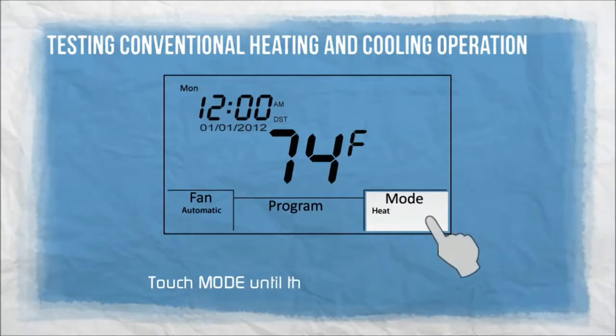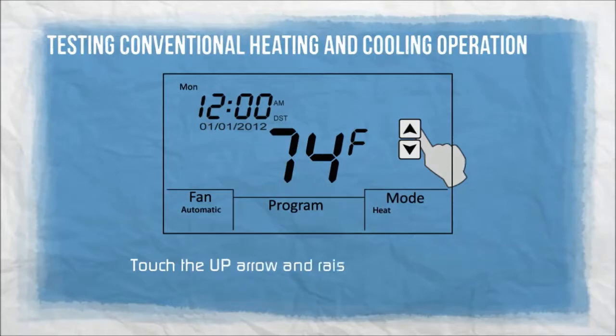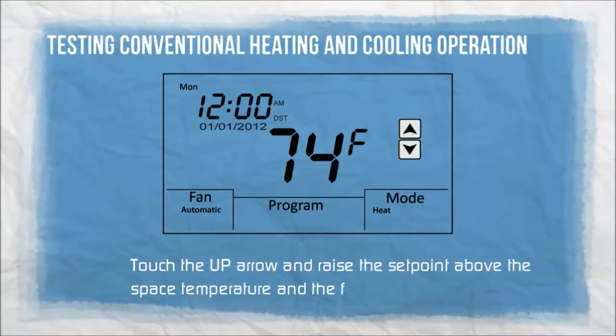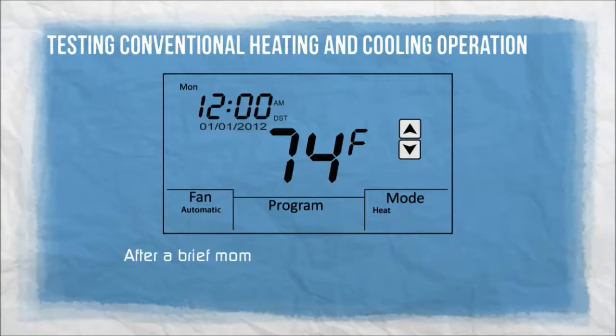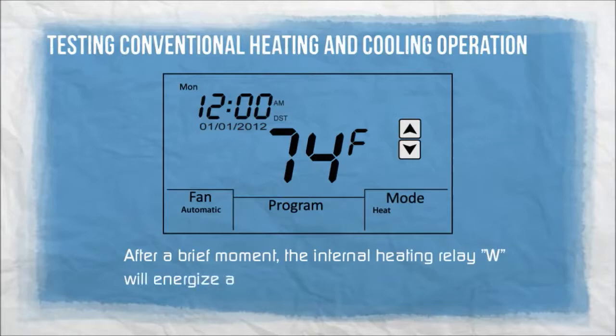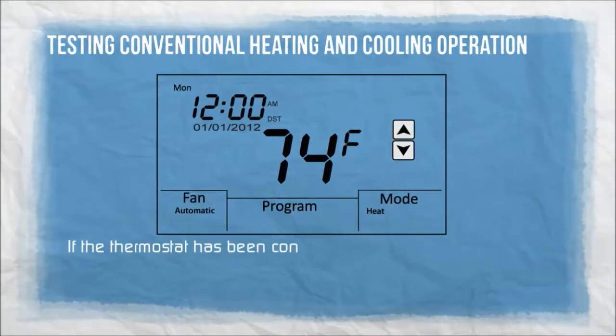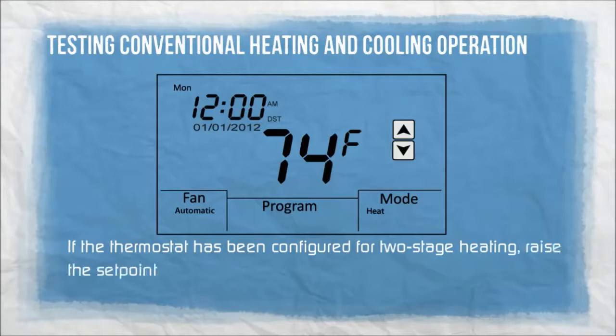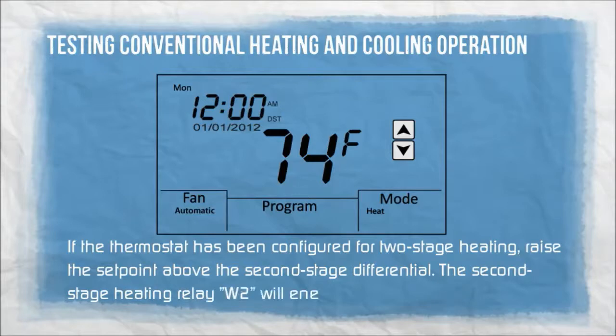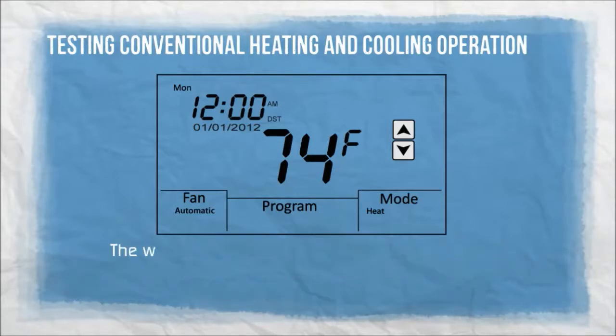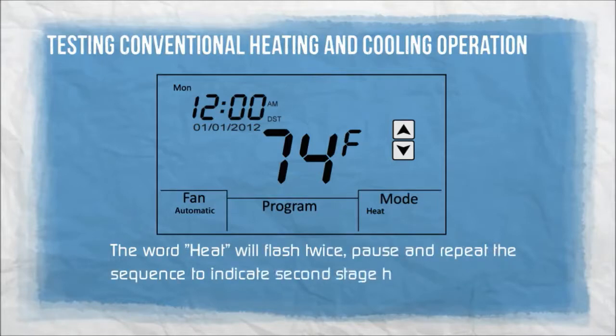Touch MODE until the word HEAT appears. Touch the up arrow and raise the set point above the space temperature and the first stage differential. After a brief moment, the internal heating relay W will energize and the heating system should operate — the word HEAT will flash continuously. If configured for two-stage heating, raise the set point above the second stage differential; the second stage heating relay W2 will energize. The word HEAT will flash twice, pause, and repeat to indicate second stage has been energized.